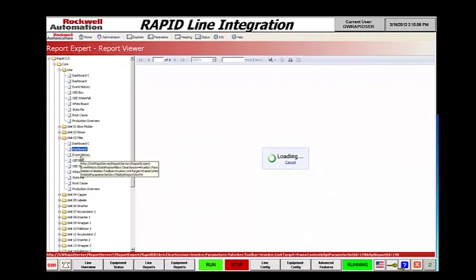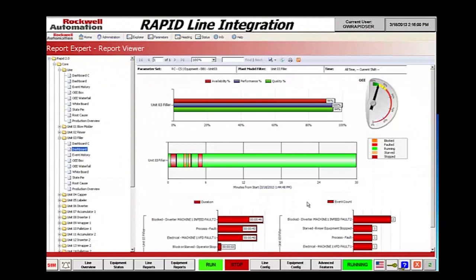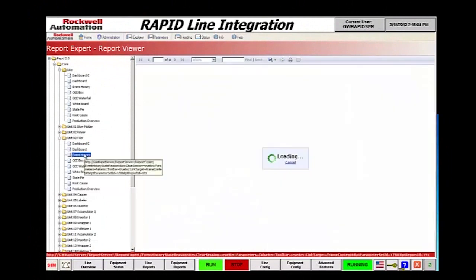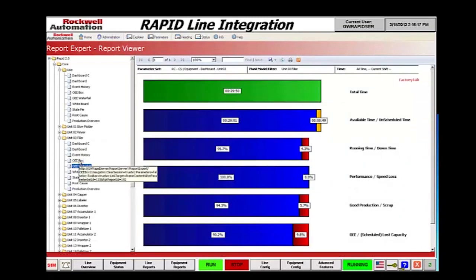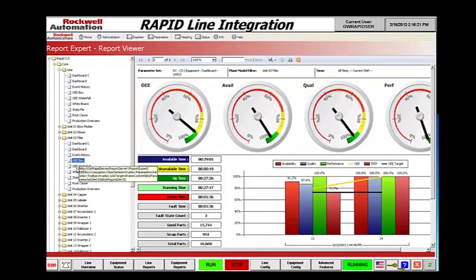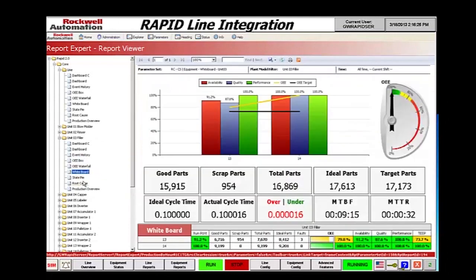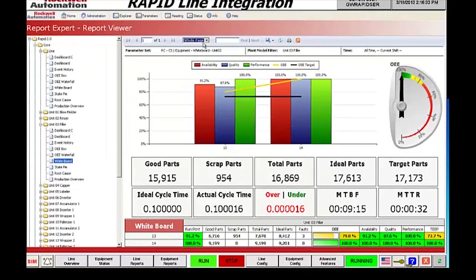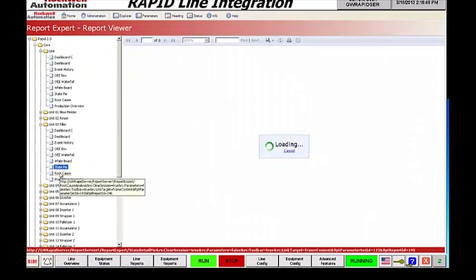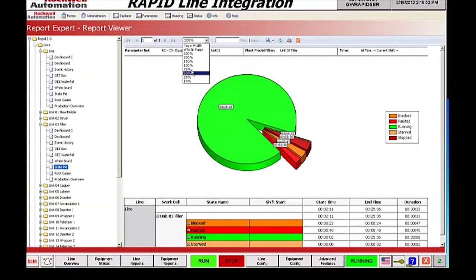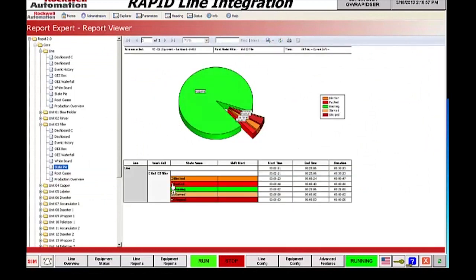In this case, we are extracting out filler-based reports. A similar dashboard report shows total top downtime durations and events. Overall event history can be shown, giving a detailed listing of the actual events of the machines — the faults, when the faults occurred, and the duration of the faults. An overall OEE waterfall report is similar to that line-level report shown earlier, but on the individual machine level, as well as a dashboard report giving good fault downtime, mean time between failures, and mean time to repair — all collected on a machine-by-machine basis. There is also a whiteboard broken down on an hourly basis for each machine, and a root cause state pie chart listing the individual states of the machines. The table below breaks down the actual events in durations of time and starting and stopping of the events.